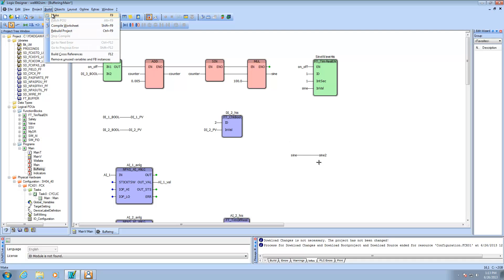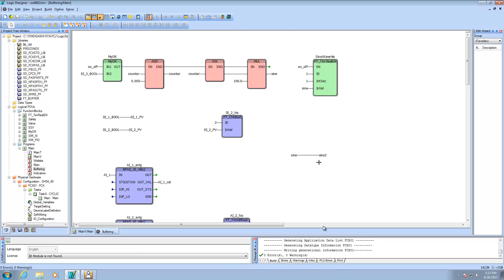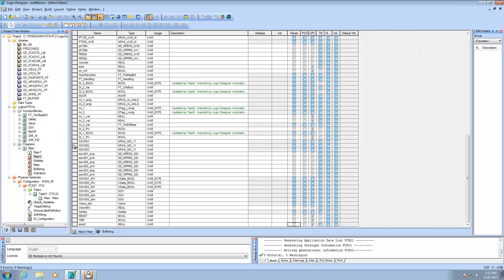I'm going to do a make on this and check that there are no problems with my code. Next I'll go to my main variable sheet. Down at the bottom you'll see sine2 as a real variable. The important thing is to make sure the OPC box is checked. This really has less to do with OPC and more to do with exposing the sine2 variable for external projects to read it. FastTools is going to be the external project reaching into the controller to read that variable.